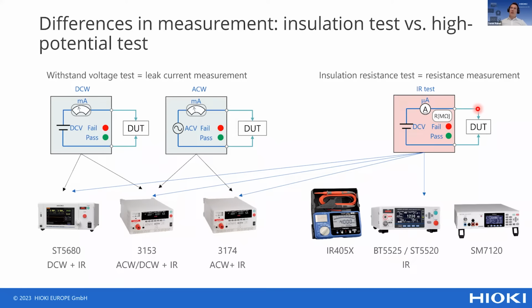And from the knowledge of our device, we know that we have a very stable DC voltage being applied, and the current we are detecting, we can then calculate the resistance value. And this gives the manufacturer or the tester an indication of the resistance value or the insulation value of the device being under test.